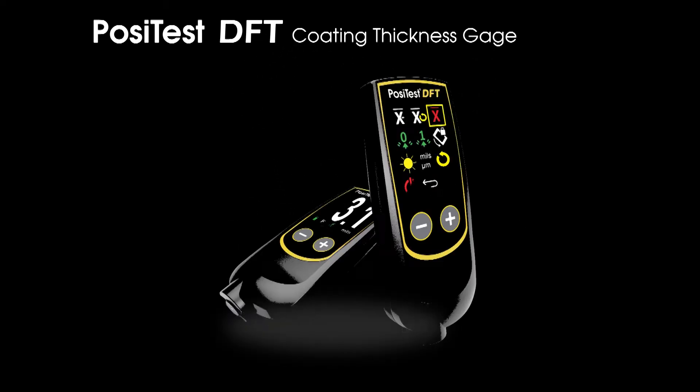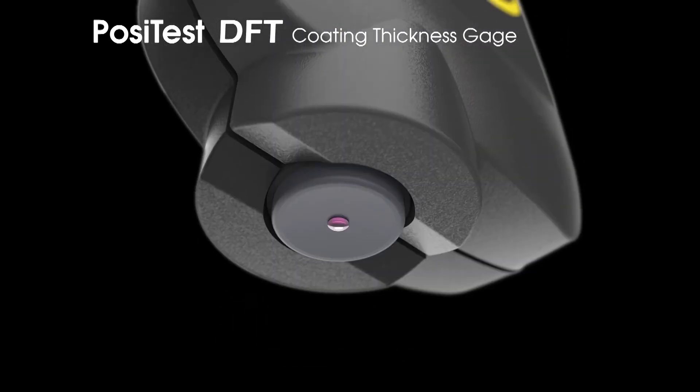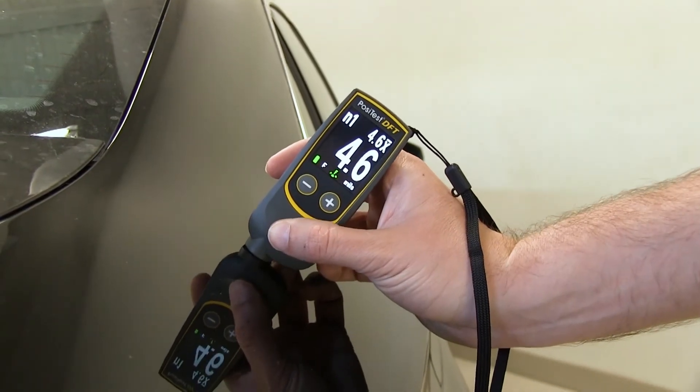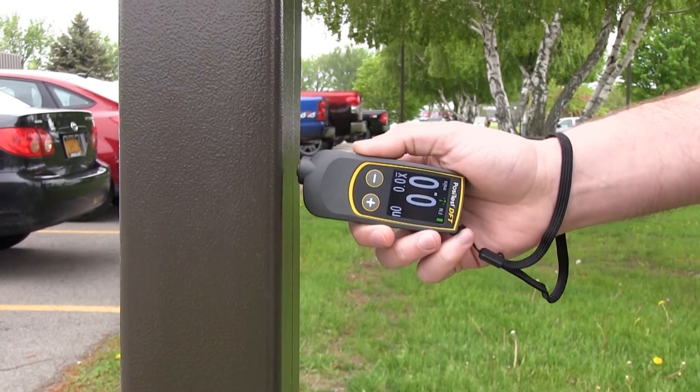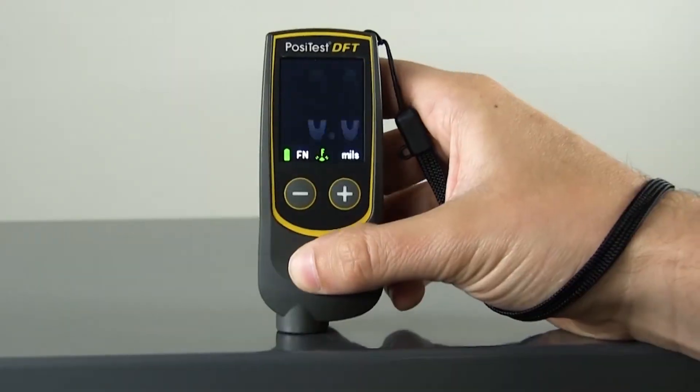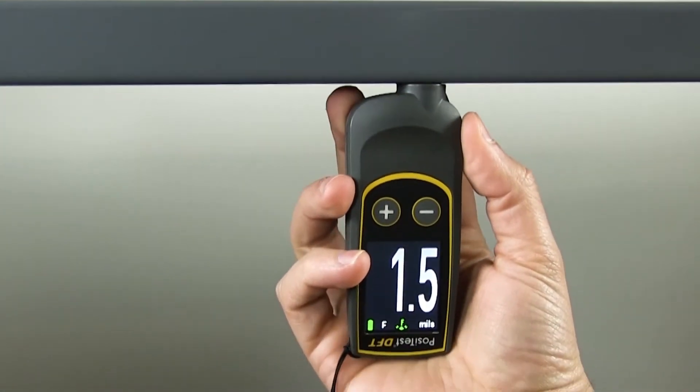The Positest DFT features the same probe technology as the Positector 6000 in a simple, economical format. It's ideal for users who want to measure coating thickness up to 1 mm or 40 mils on metal substrates and don't need the memory, software, or probe interchangeability of the Positector platform.